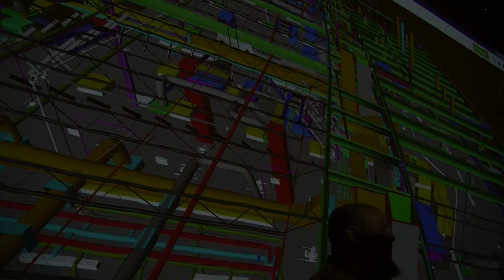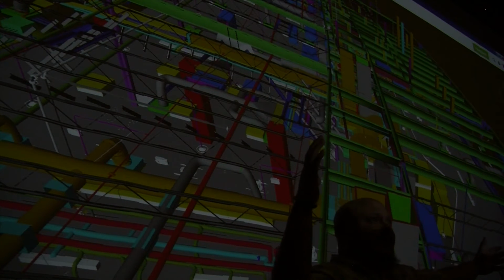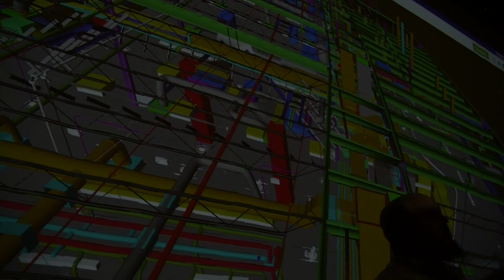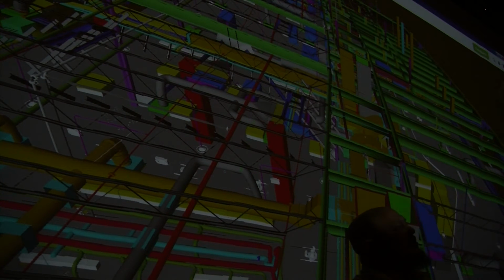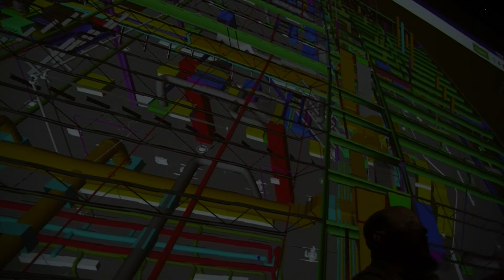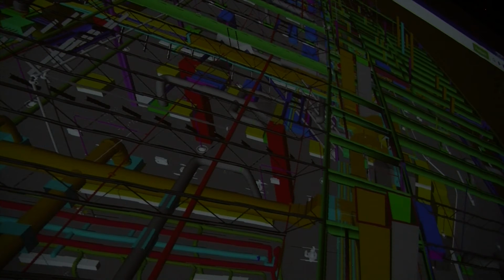So by doing this, you no longer need to have the giant air handler on the roof that's actually heating air to a certain temperature. Because as those terminal units heat up the air in the building, the ERVs suck in the new air, expel the old air, transfer that energy, and the VAVs can now adjust locally the air temperature as necessary for the occupant. It's basic thermodynamics. That's why UNM forces you guys to take Physics 101 and 102.